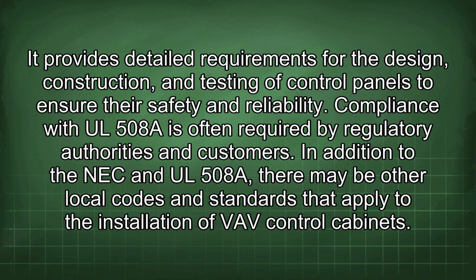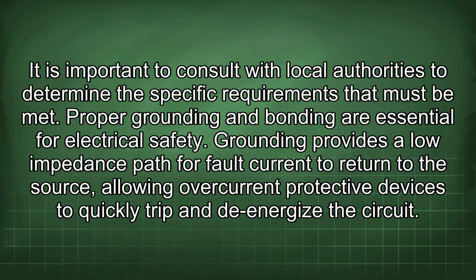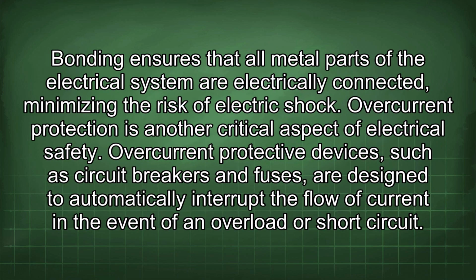In addition to the NEC and UL 508A, there may be other local codes and standards that apply to the installation of VAV control cabinets. It is important to consult with local authorities to determine the specific requirements that must be met. Proper grounding and bonding are essential for electrical safety. Grounding provides a low impedance path for fault current to return to the source, allowing overcurrent protective devices to quickly trip and de-energize the circuit. Bonding ensures that all metal parts of the electrical system are electrically connected, minimizing the risk of electric shock.